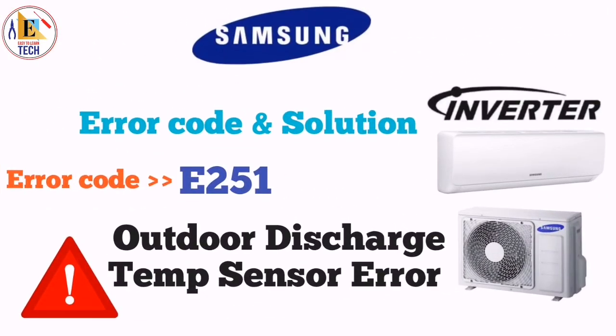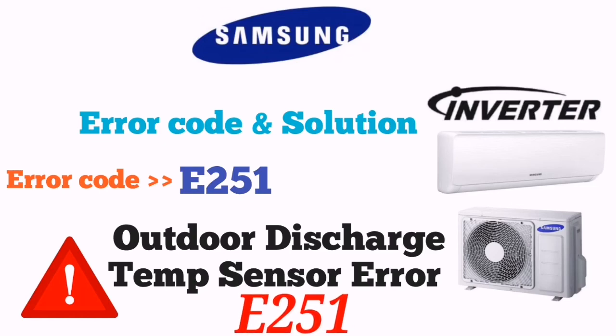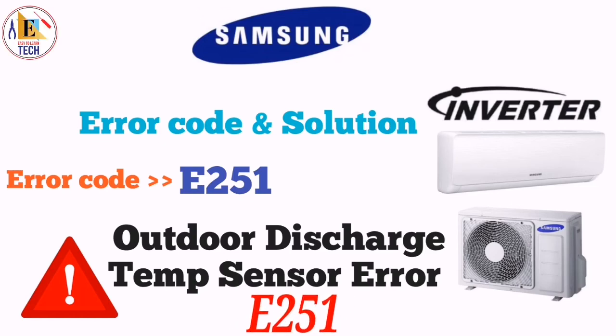When you see error E251 in your outdoor unit, it means outdoor discharge temperature sensor error, and you have to follow the same process of the sensor error for E221. But in this case, the resistance should be 200 kilo ohms plus minus 3% at a room temperature of 25 degrees Celsius. You can follow the previous steps for the sensor and sort out the issue and make your system work.